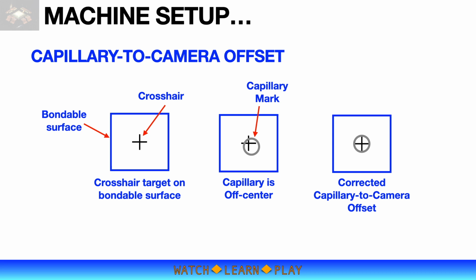For proper bond placement, it is very important that the capillary tip and camera crosshair are, as much as possible, perfectly aligned. When you create a bond program, you use the crosshair to teach the bond placement. And when you do the actual bonding, the center of the capillary will land on the crosshair. So if the capillary is off-centered to the crosshair, then the bond placement will not be correct. Every time you change the capillary, the capillary-to-camera offset should be taught. A quick illustration is shown on this slide. A capillary mark or impression is made on a bondable surface. Initially, the capillary mark will be off-centered to the crosshair. After adjustment, the capillary should be aligned to the crosshair.